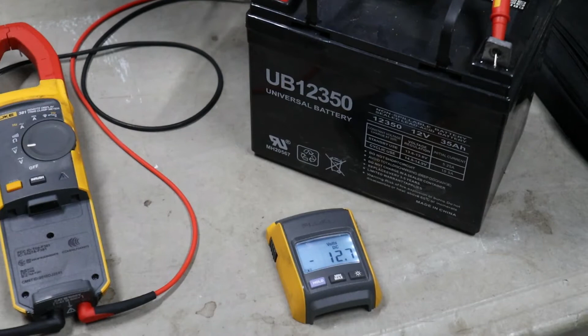So with this demonstration, we'll go on next to the ohms and continuity tests. So we'll start off with continuity, which is a very helpful way of measuring and troubleshooting circuits when you're wanting to test wires between, let's say, phase and ground, just to make sure you have no shorts before you energize any electrical. So you can hear the tone when you touch the leads together as a direct short. Anytime you have a short, you'll hear that tone, and it'll give you a resistance value like very low, around 0 or just around 0.